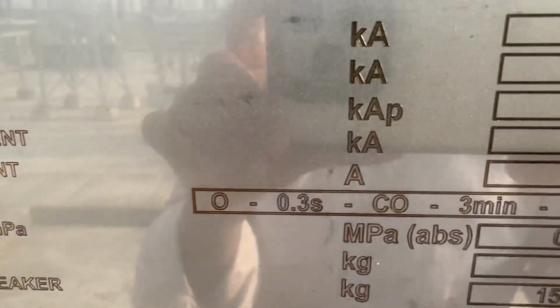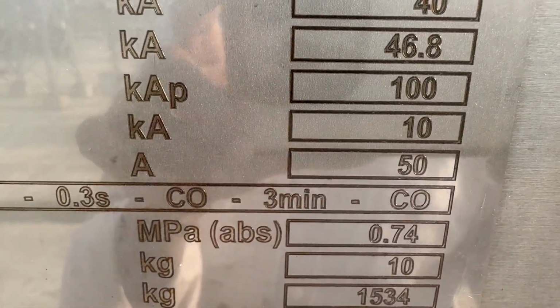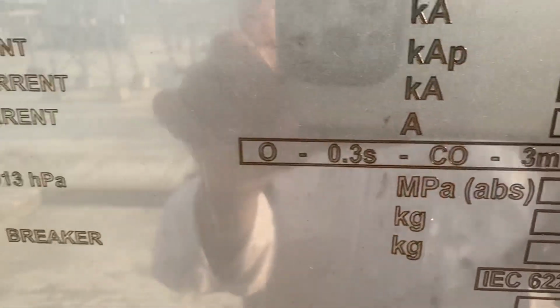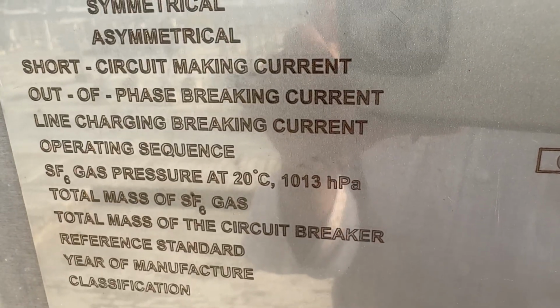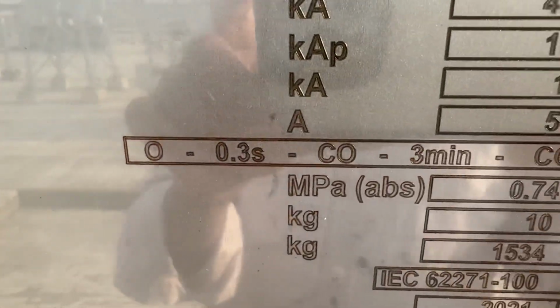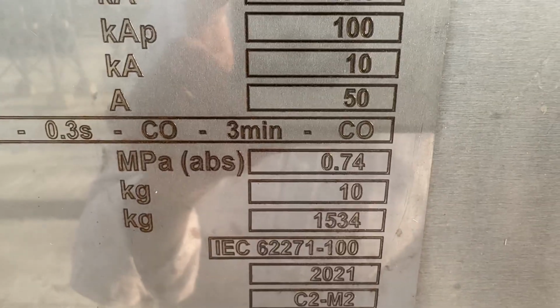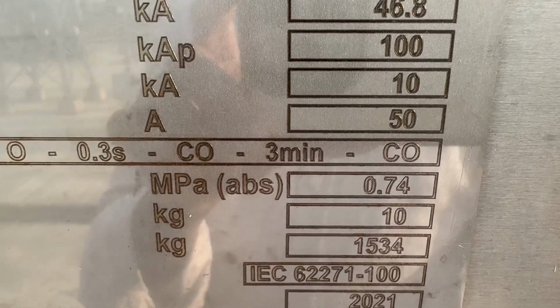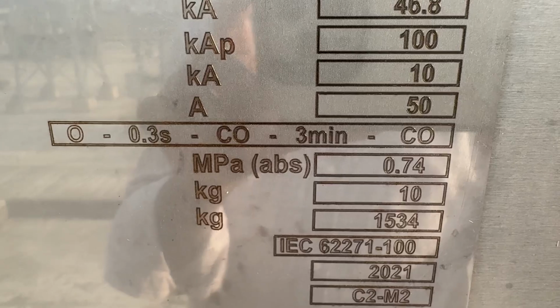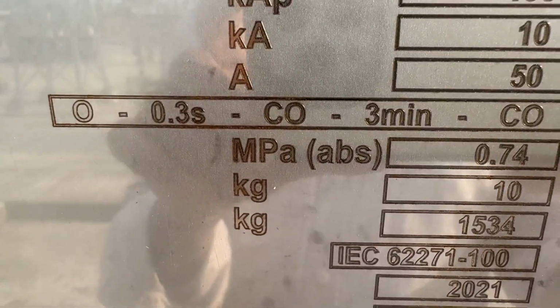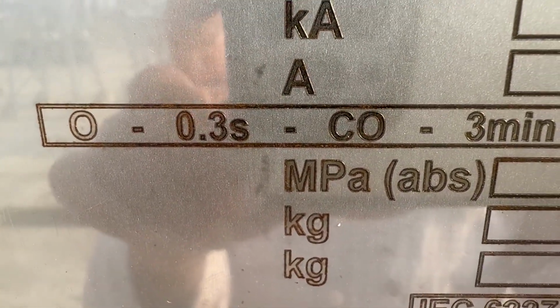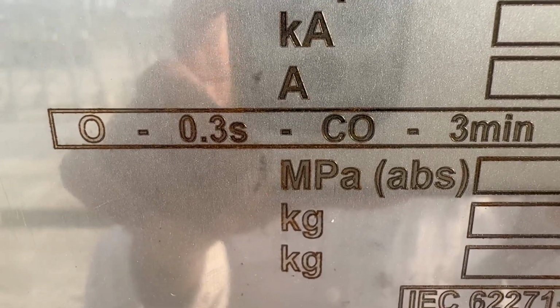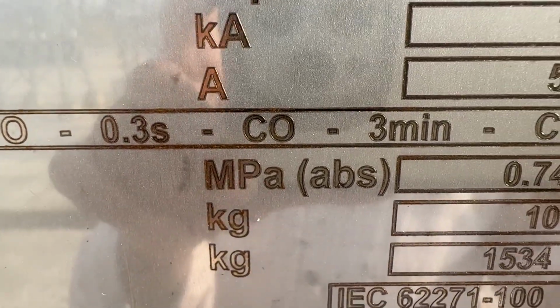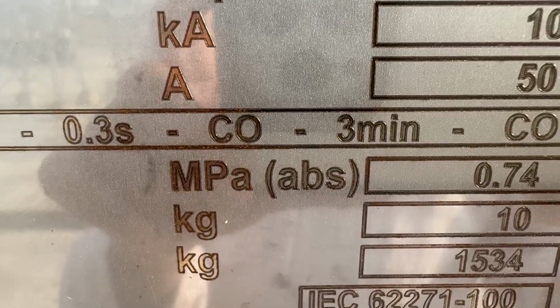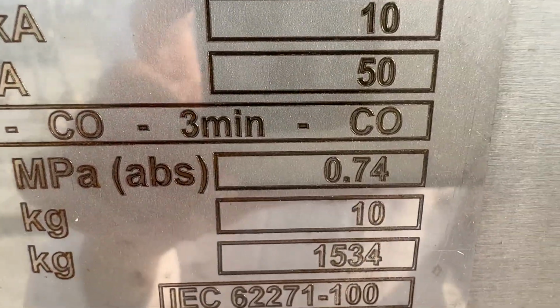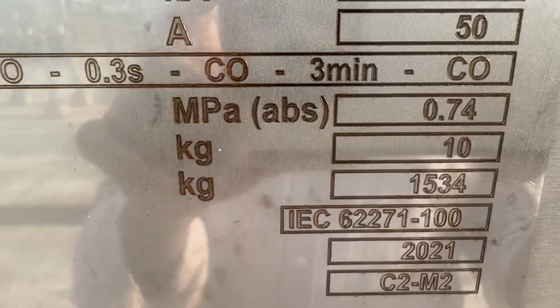Out of phase breaking current is 10 kiloampere. Line charging breaking current is 50 ampere. Okay, this is the operating sequence: open, wait 0.3 second, then close and open again, then wait 3 minutes, then close and open again.